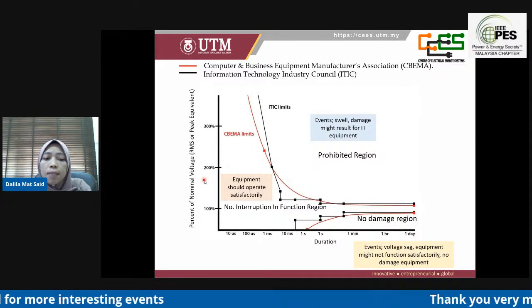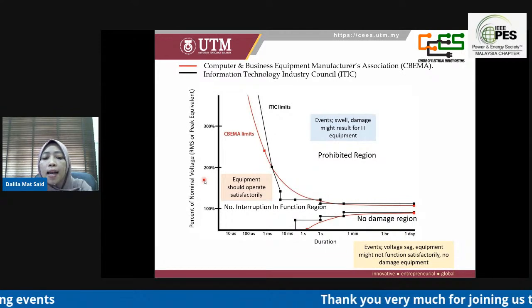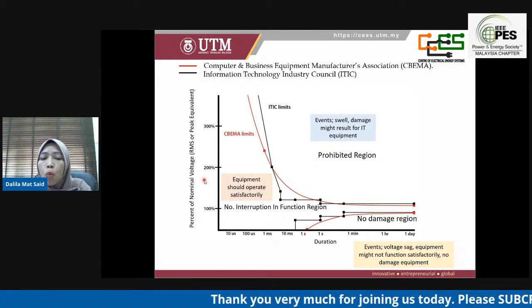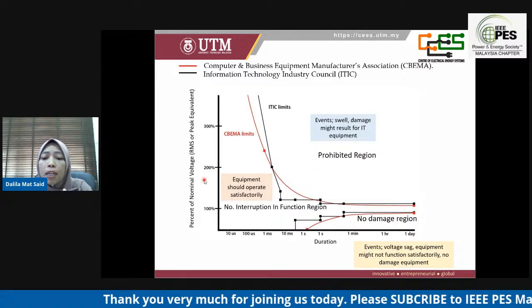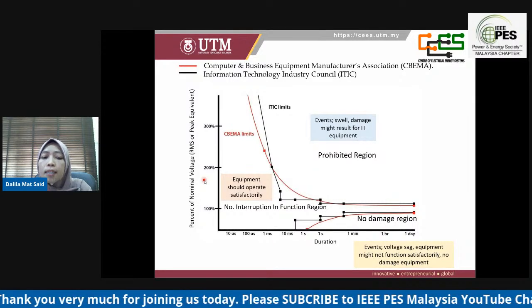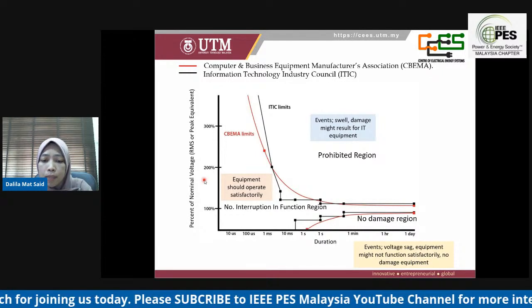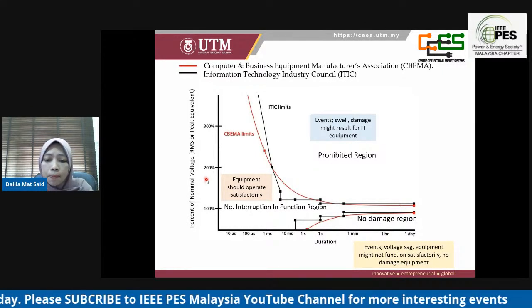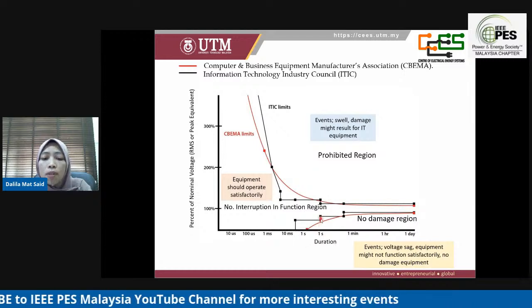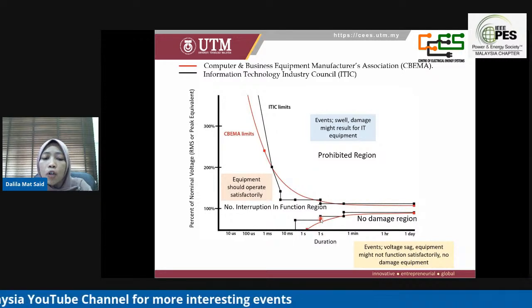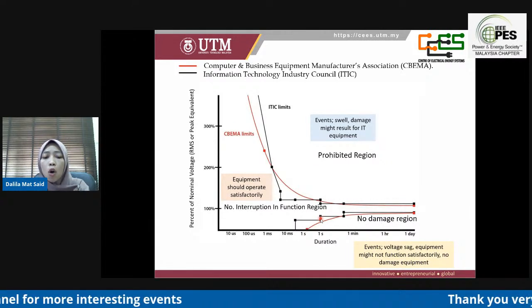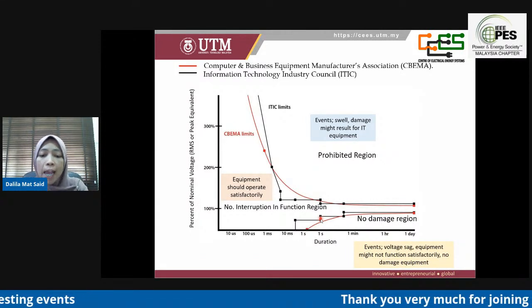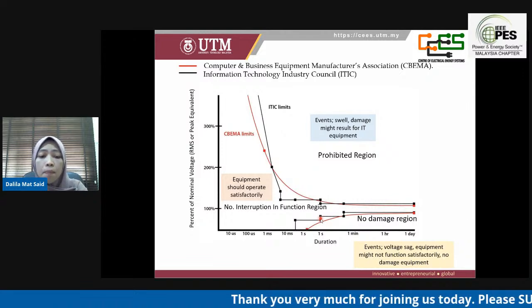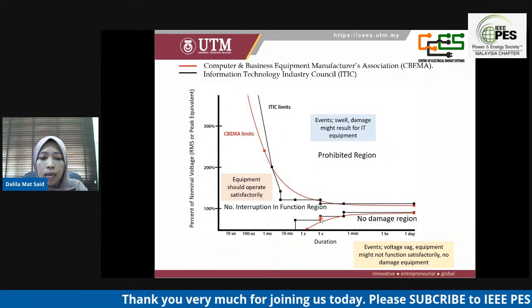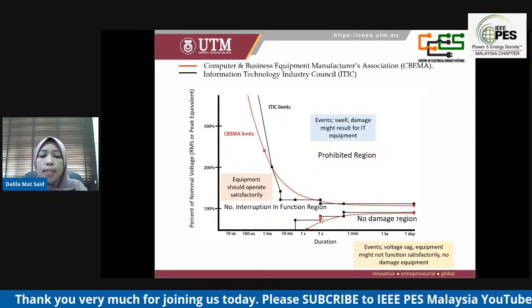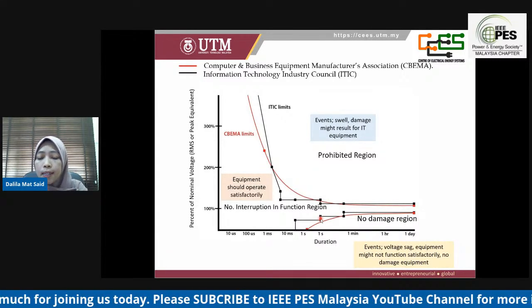In 2000, the CBEMA curve was renamed the ITIC curve, where the ITIC curve is published by the Information Technology Industry Council, formerly known as CBEMA. This provides an AC voltage boundary that most information technology equipment can tolerate or ride through without experiencing unexpected shutdown or malfunction. Information technology equipment could include single-phase computers, printers, and scanners.